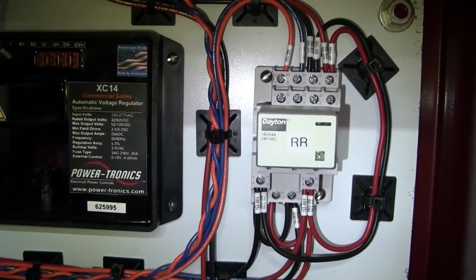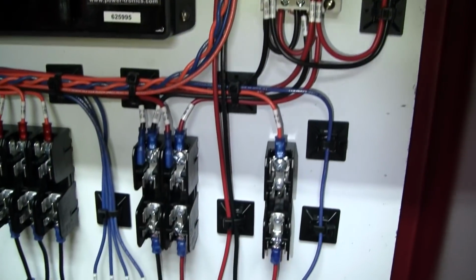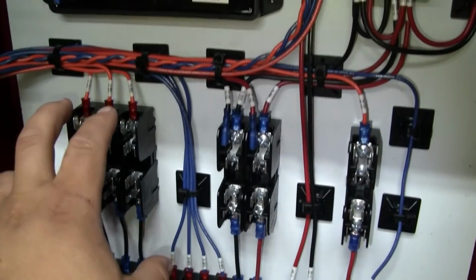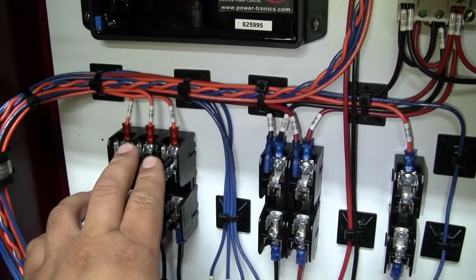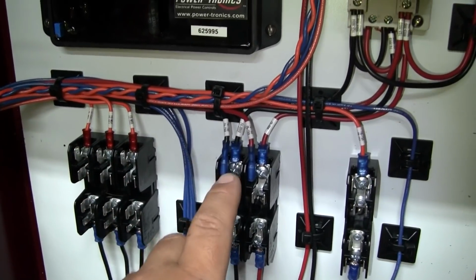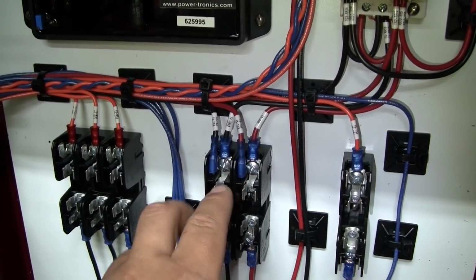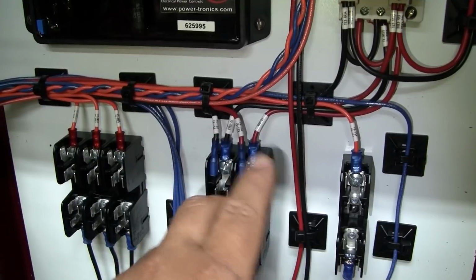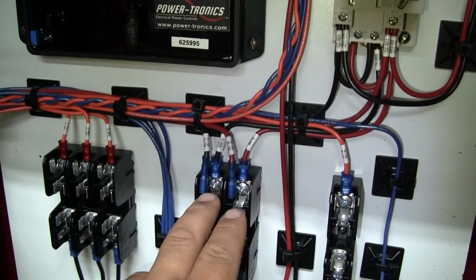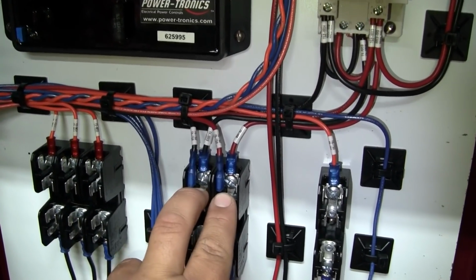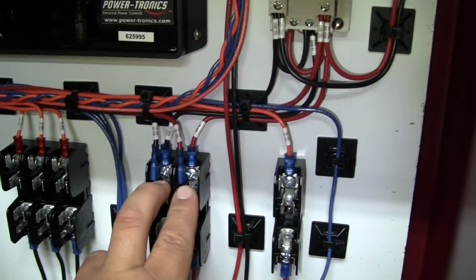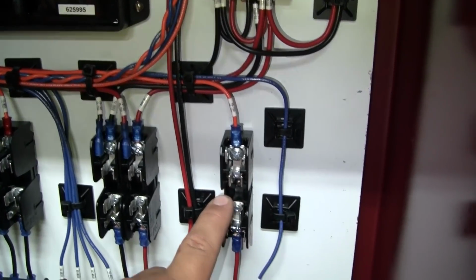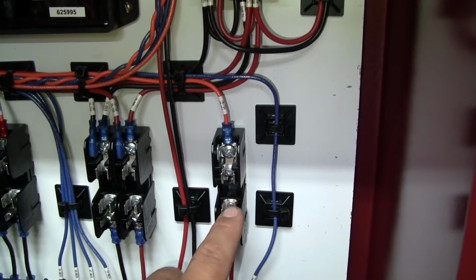Regulator relay comes down, we got fuses here. 3 fuses, 1 for each phase for the metering. 2 fuses, which is regulator power and regulator control circuit power, that's operating off of 2 phases, 2 legs of the generator output. And then we got a single fuse here, which is the DC fuse.